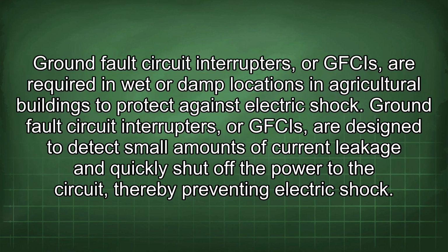Ground fault circuit interrupters, or GFCIs, are required in wet or damp locations in agricultural buildings to protect against electric shock. GFCIs are designed to detect small amounts of current leakage and quickly shut off the power to the circuit, thereby preventing electric shock.